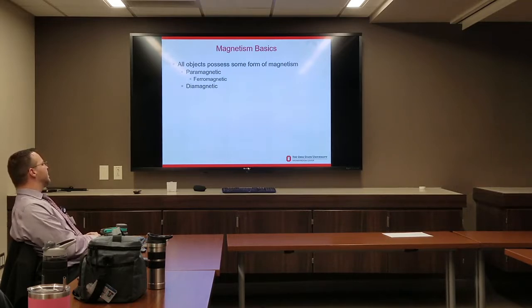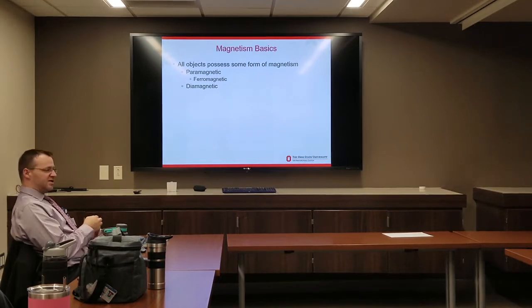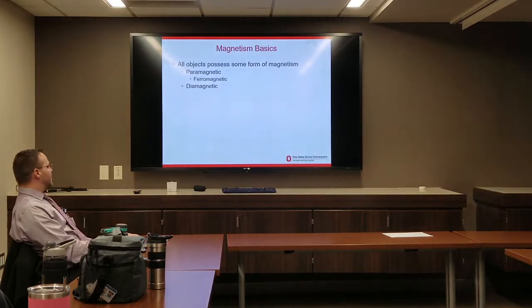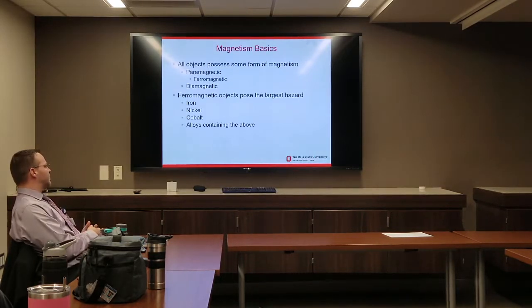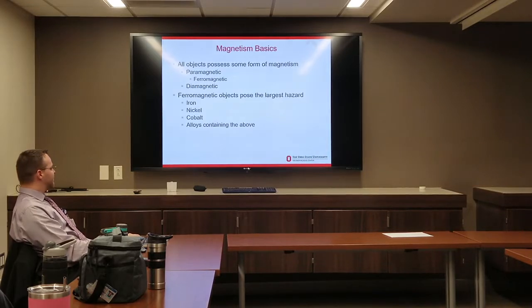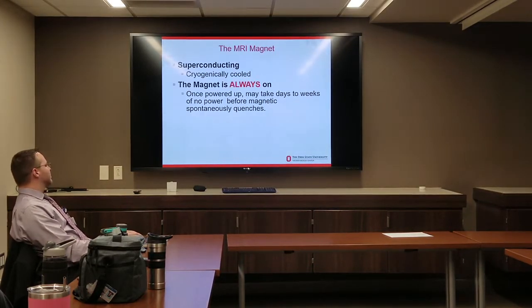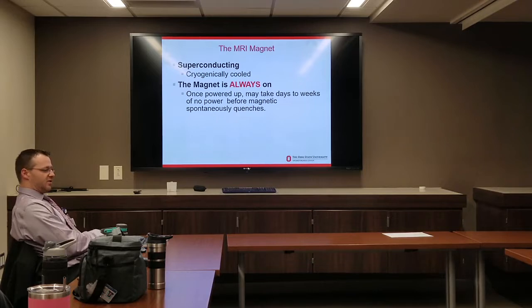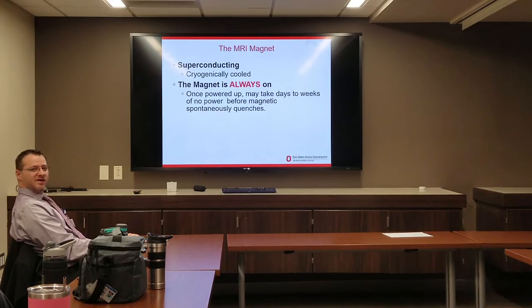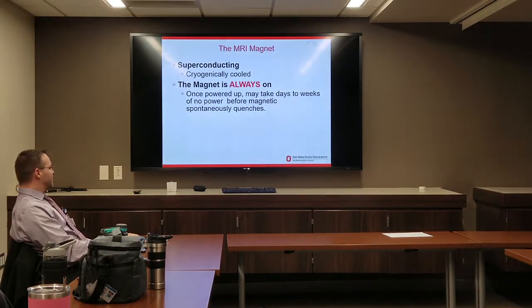Some basics of magnetism: all objects possess some form of magnetism — they could be paramagnetic (a subclass of which is ferromagnetism, our primary concern) or diamagnetic. Ferromagnetic objects pose the largest hazard — anything made of iron, nickel, cobalt, or alloys containing those metals are ferromagnetic. The MR magnet is a superconducting, cryogenically cooled magnet. It is not off at any time — it is always on, unless you hit the quench button or there's a spontaneous quench. Always assume it's on unless you know otherwise.